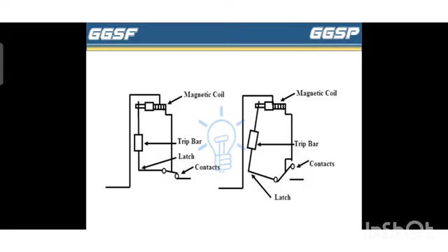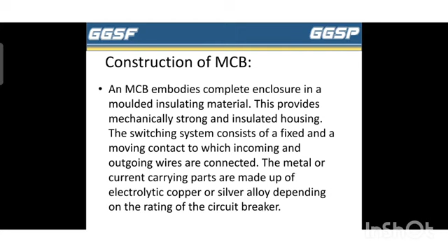An MCB is completely enclosed in a molded insulating material. This provides a mechanically strong and insulated housing. The switching system consists of a fixed and a moving contact, to which the incoming and outgoing wires are connected. The metal or current carrying parts are made up of electrolytic copper or silver alloy, depending on the rating of the circuit breaker. This is the construction diagram of the MCB, miniature circuit breaker.